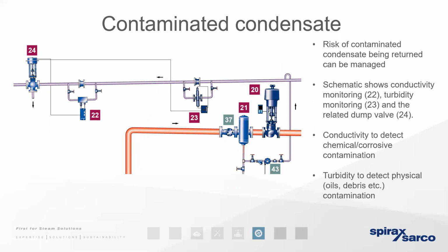And it also means that the acids and the fats can be carried from the boiler in the steam and potentially cross-contaminate another process. So a lot of clients are still dumping condensate to waste to protect the process, and that's absolutely the right thing to do, but only when there is a risk of contamination.